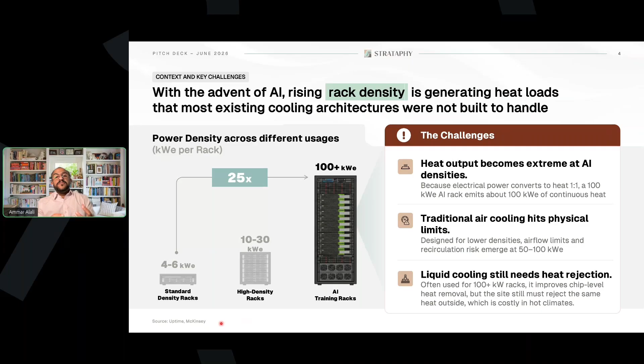If you don't dissipate this heat, the problem builds up. As mentioned, whenever you hear about data center size in terms of compute power, you can assume a similar volume in thermal units needs to be dissipated - a 100 megawatt electricity size data center typically requires a 100 megawatt thermal cooling system. If you don't meet that demand at a similar size, you get a buildup of thermal energy, which typically results in performance limitation, equipment failure, efficiency reduction, and all of this could translate to reduced revenue or output - tokens produced by the data infrastructure - especially during hours when it's relatively hotter outside.